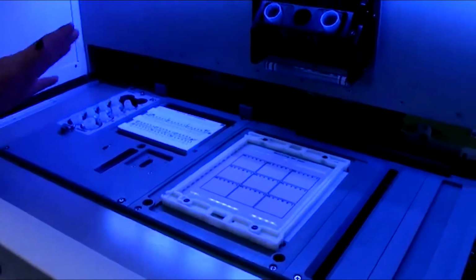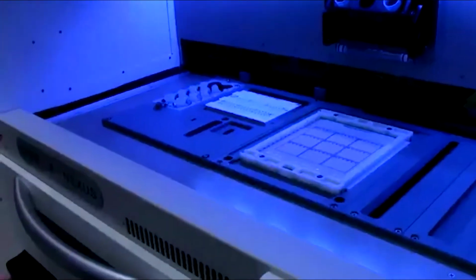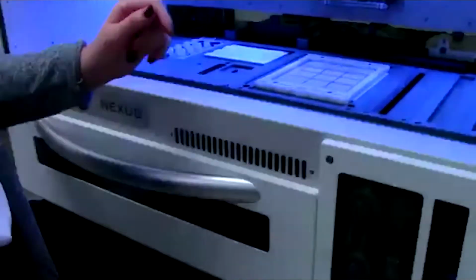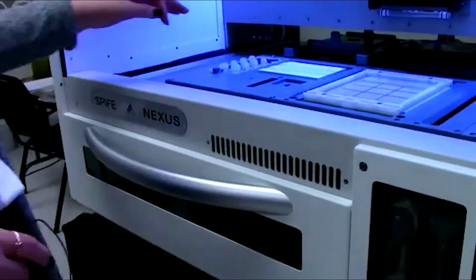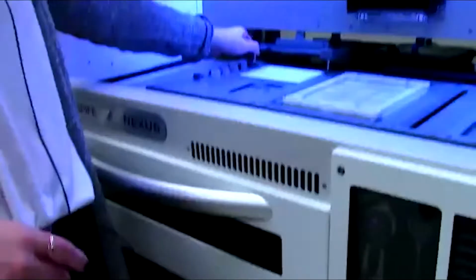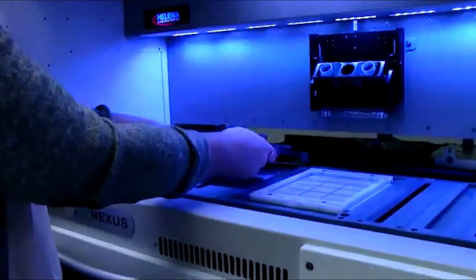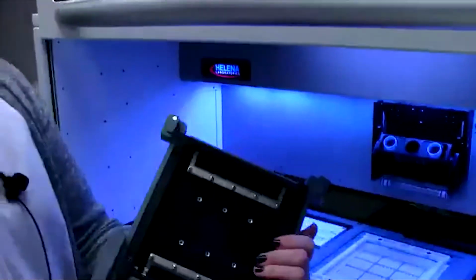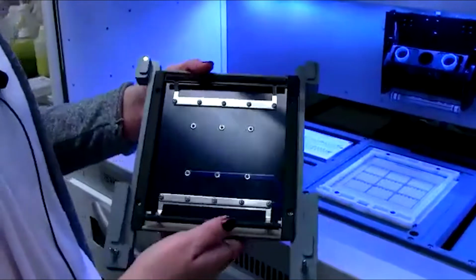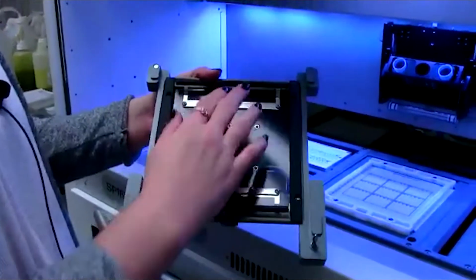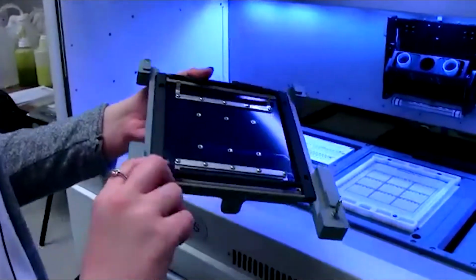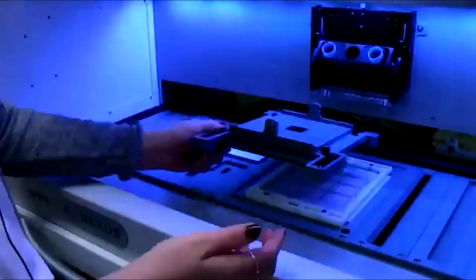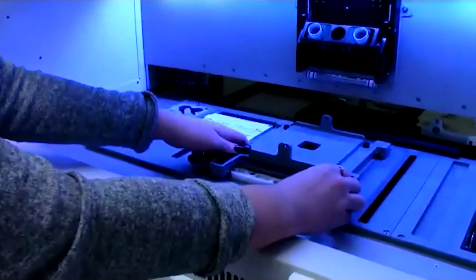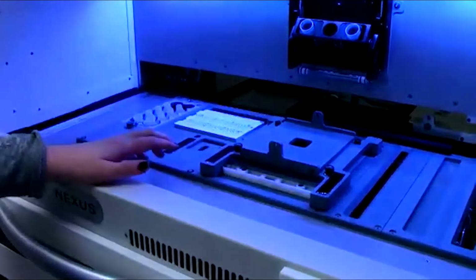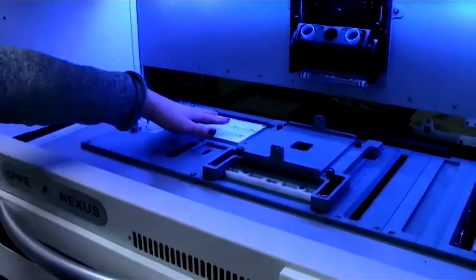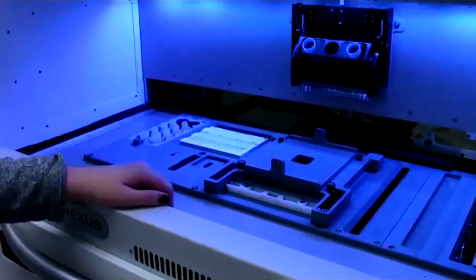All right, so now we're all set up to run. I just want to point out a couple of the pieces that we haven't talked about so far. This is our platen cover, and it's where our electrodes are for electrophoresis. The bottom side of it has two electrodes and these pegs which connect to the machine. During a run, it's brought forward for electrophoresis, and also to cover the gel to keep it from drying out while the sample is being loaded into the sample tray.